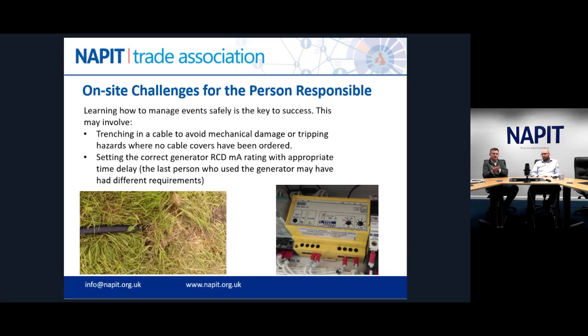So it's really important to make sure that there's effective selectivity in the distribution, so that at the source you have an RCD that's rated higher, say 100 milliamps or 300 milliamps. But the crucial thing is it must have delay built in, so that if there's a fault, we disconnect the RCD on the final circuits closest to the fault, not the ones at the source of supply. Because to put it bluntly, you don't want someone plugging in the kettle backstage, tripping the generator and everything going dark. So we want the RCD at the final circuit to actually disconnect before the rest. That means you need delay built into the system.